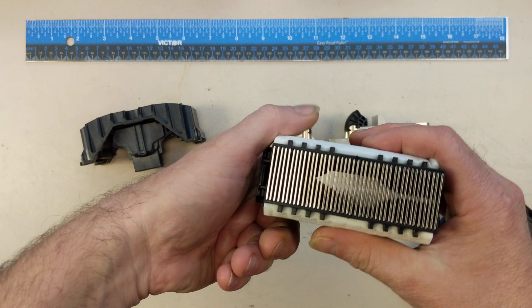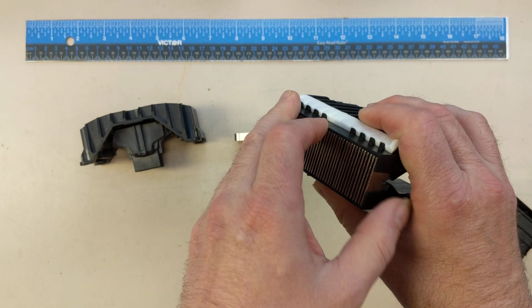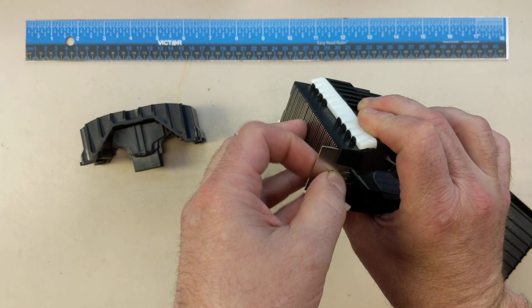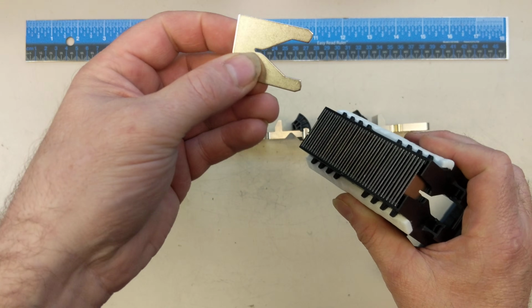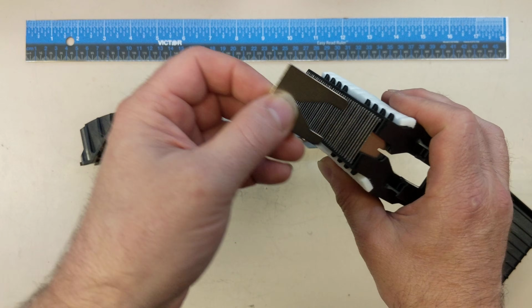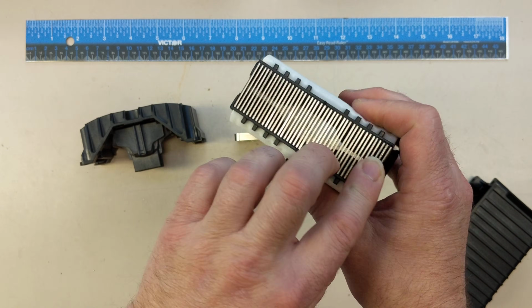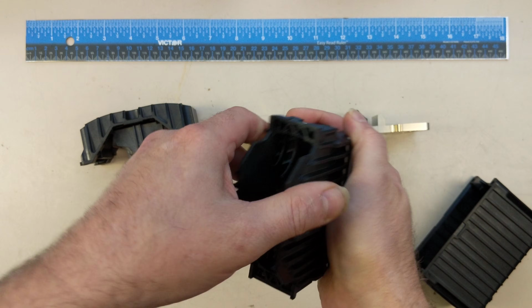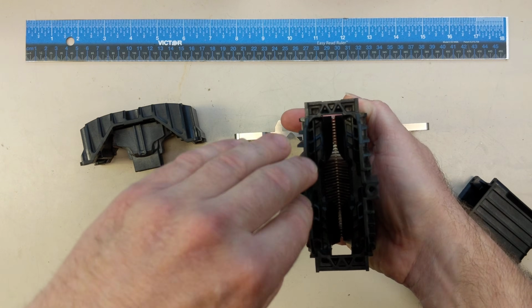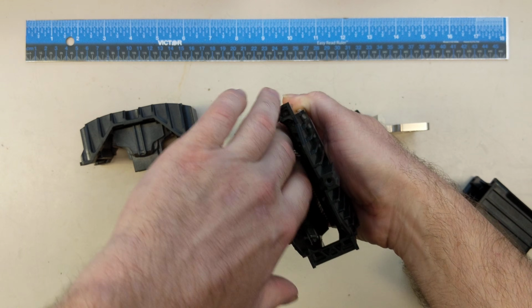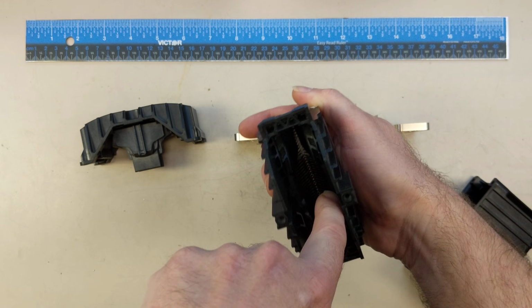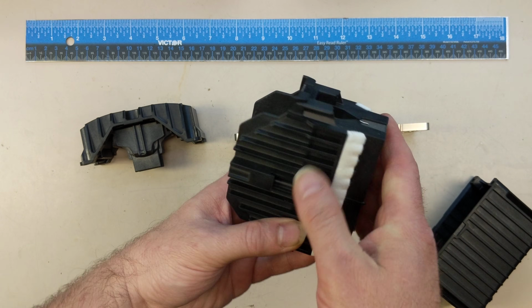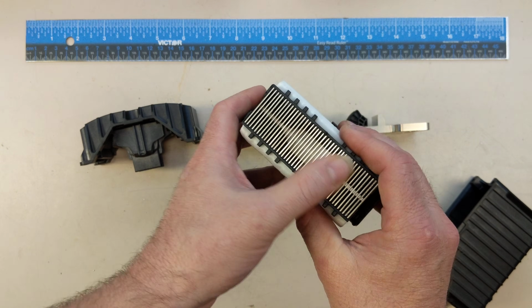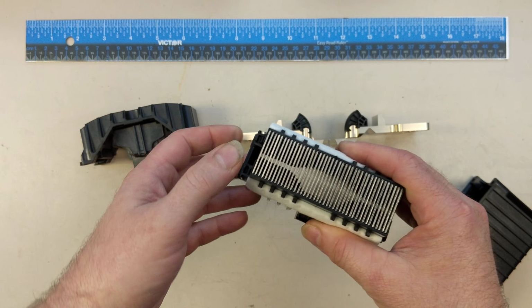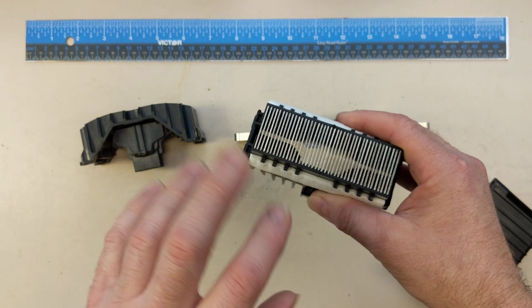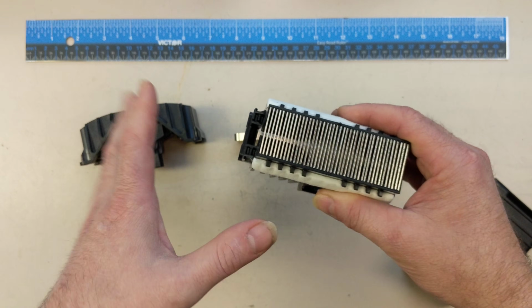So there's all these little metal blades - let's see if I can get one out. They're just mild steel blades, gapped in here so that as the hot gas comes out of that explosive charge, it slams the arc into this, which breaks it into lots of little pieces and also cools it, because this metal acts like a heat sink, spreading the arc, breaking it into pieces, and cooling it.